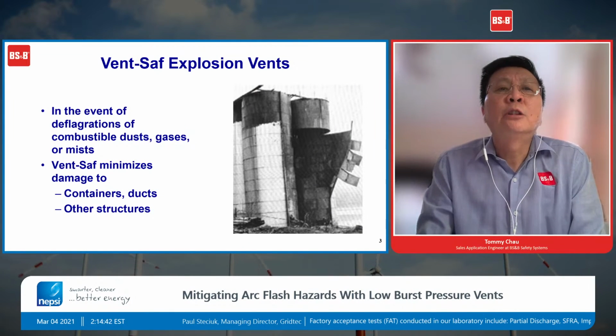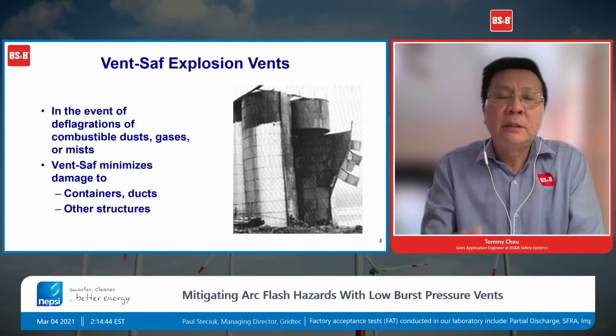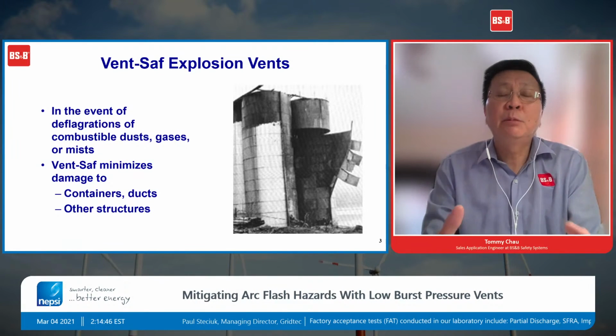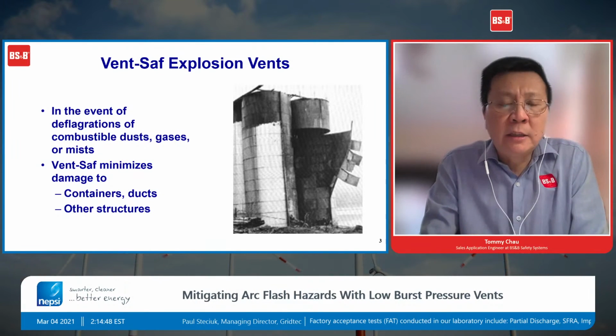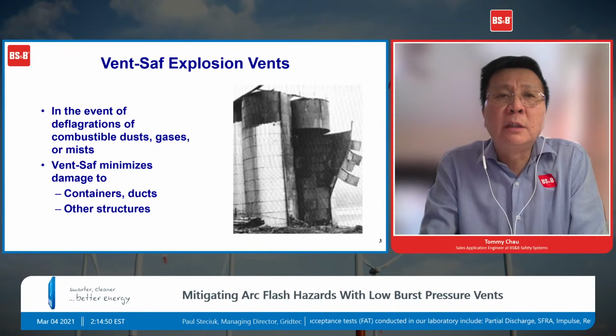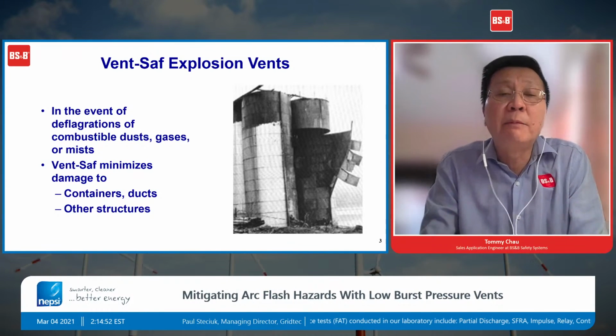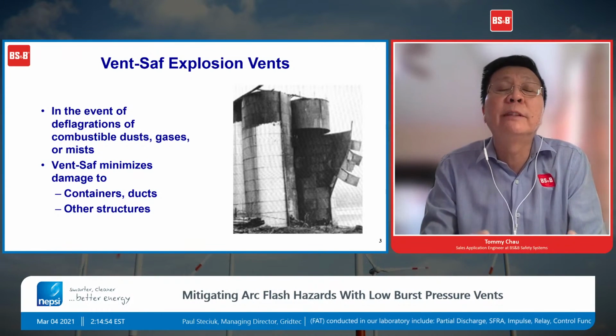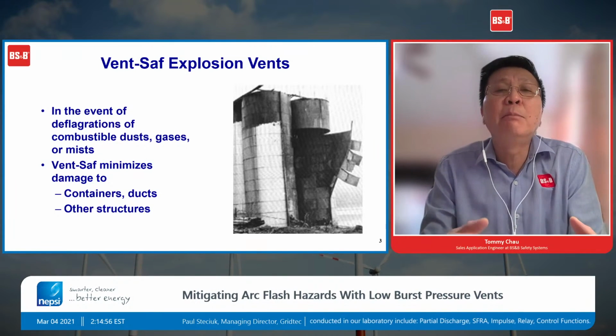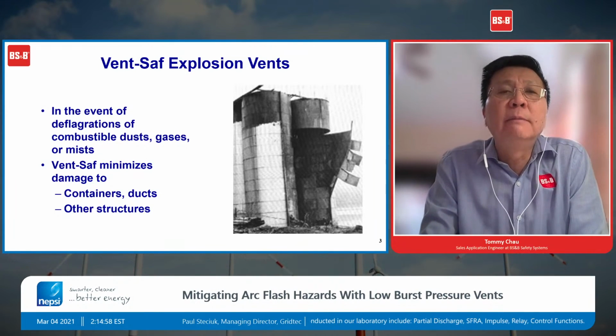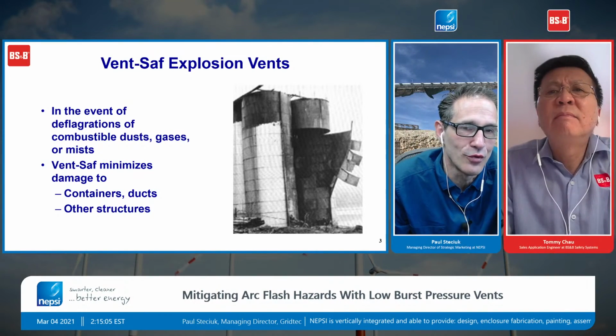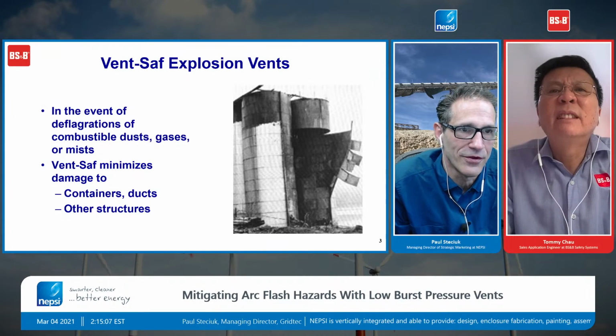Okay, so in the event of a deflagration, the explosion vent will minimize the damage to your equipment. Just because you have explosion panel doesn't mean you won't have an explosion. The explosion vent will activate and minimize the damage to your equipment. And Tommy, I think it's worth commenting, that's a whole silo, right, that's blowing up there?